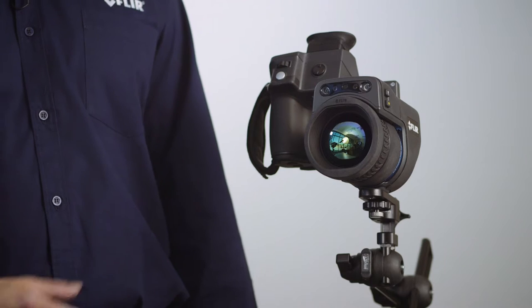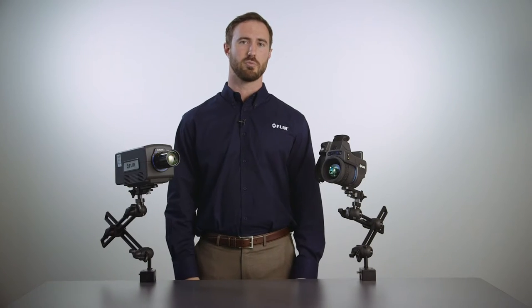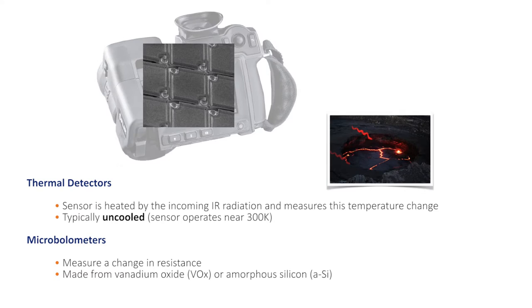Let's first address uncooled detector based cameras. This FLIR T1K uncooled detector camera has a 1024 by 768 microbolometer detector. A microbolometer is a thermal-based sensor that experiences a change in resistance when heated or cooled. With the lens of our camera, we focus infrared radiation onto the T1K detector elements. As the radiation strikes the detector elements, they heat up and their respective resistance changes.